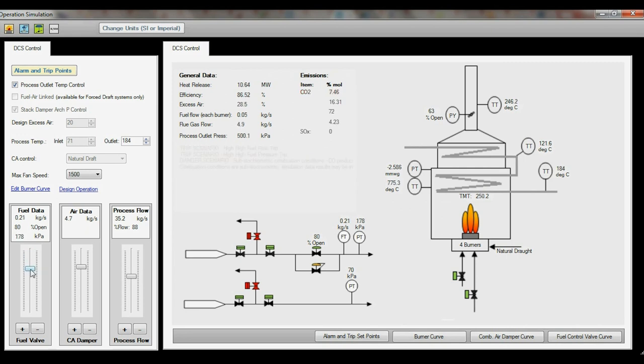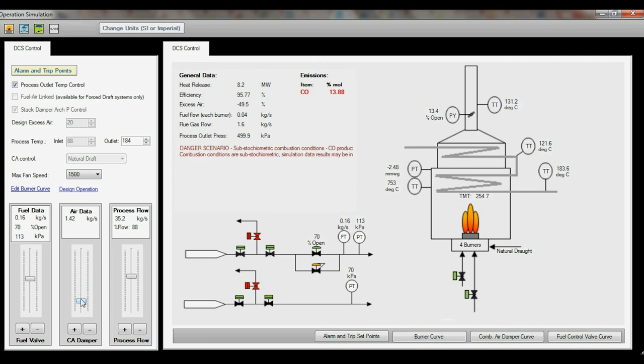Reducing the firing rate will remove the trip as shown. This useful feature allows you to gain a real sense of the safety limits of the heater as well as determining the required operational ranges for instrumentation.